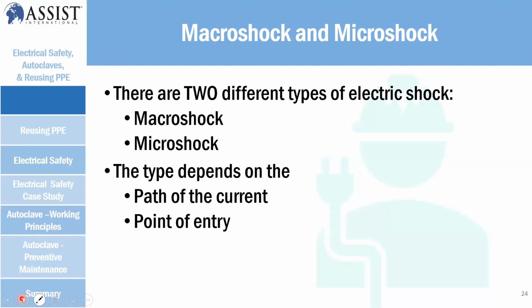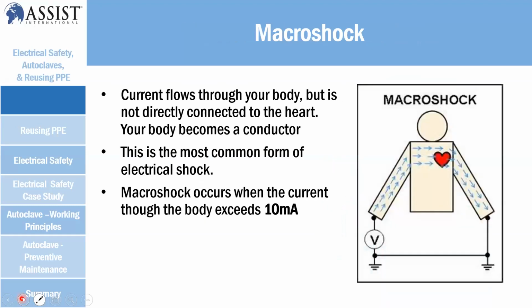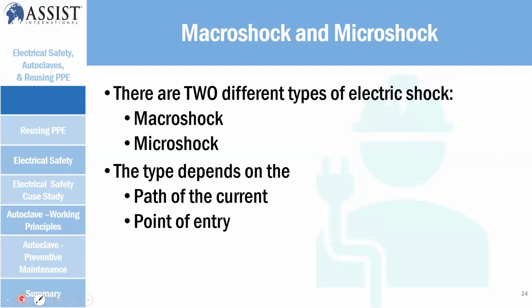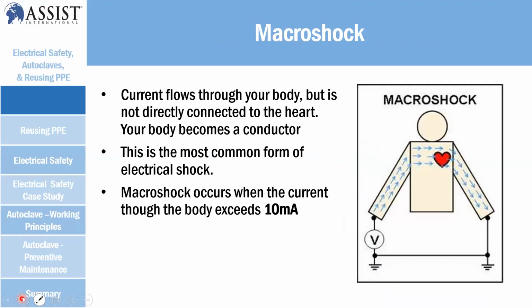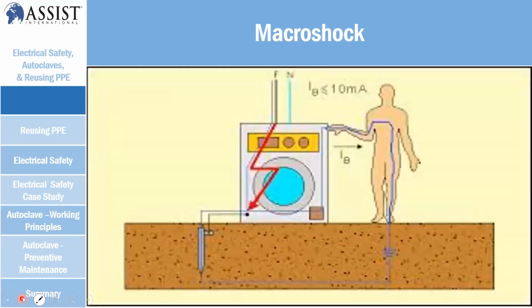Normally when you get electrocuted, in the normal condition, we call it macro shock, and there's also micro shock. These are two different scenarios. They are different types of electric shock, and they depend on the path of current and the point of entry. That's the difference. Macro shock is current that flows through your body but is not directly connected to your heart. It's not directly linked to your heart, but it passes through. Macro shock is normally somewhere around 10 milliamperes, the current through the body exceeding 10 milliamperes as it looks for a ground.